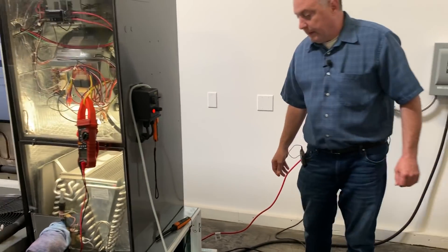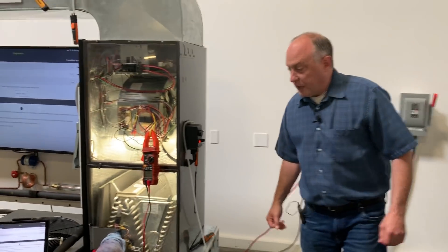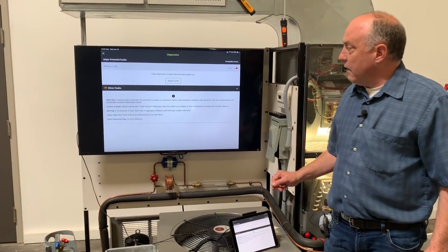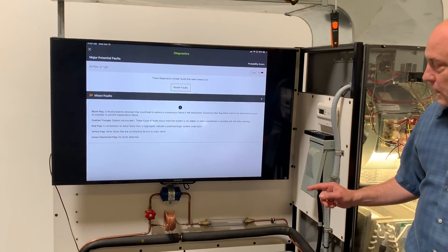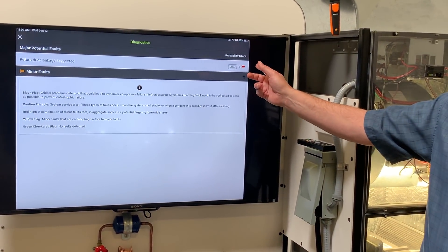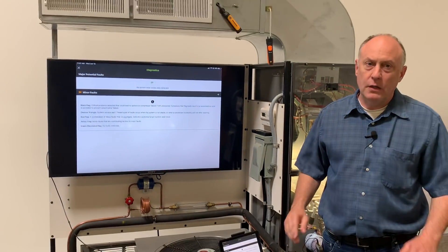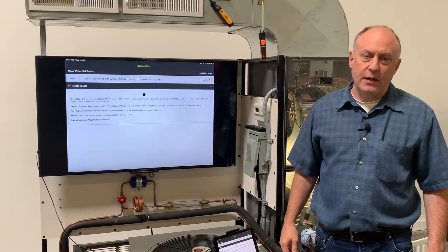We'll go ahead and unplug this here and just watch for a minute. You can see that these faults will start clearing out, and I'll reset the faults we cleared out earlier. In a few seconds, as this coil cools down, it'll go right back to no system problems detected — really fast, really easy. And now it just went to unstable because the temperature split is dropping back down, but you get an idea of how that works.